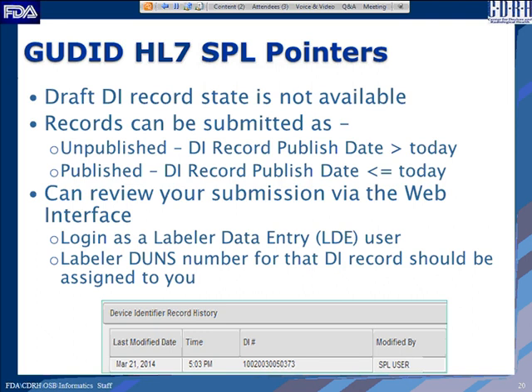The draft DI record state is not available in HL7 SPL. Via HL7 SPL you can only submit records in the unpublished or published state. Unpublished state is when the published date is set in the future; published state is when the published date is today or in the past. Once you submit an HL7 SPL submission you can review it by logging into the GUDID web interface as an LDE user, provided you have access to the labeler DUNS number used for that DI record.